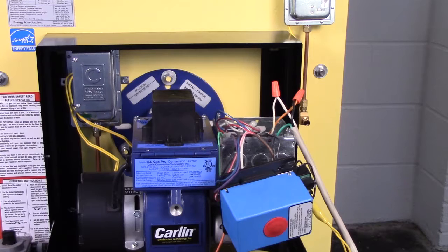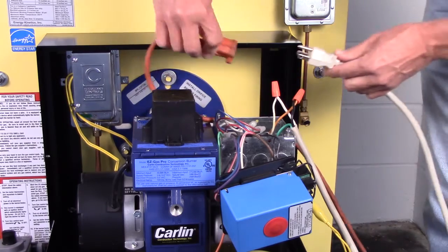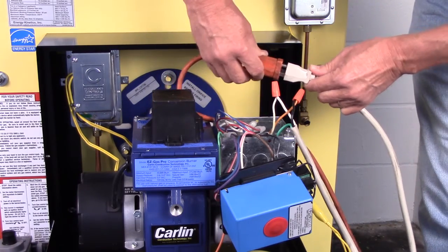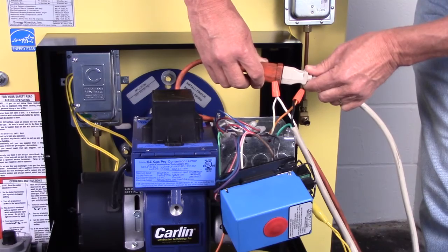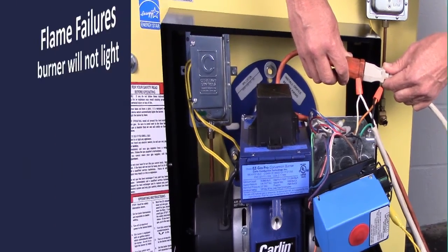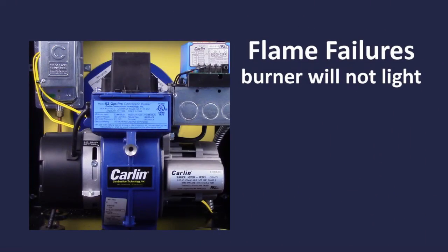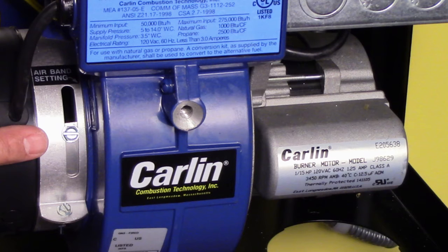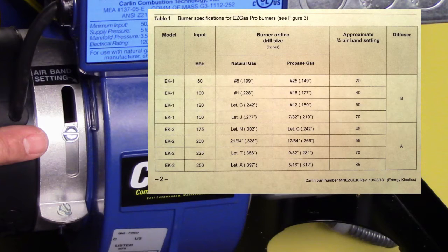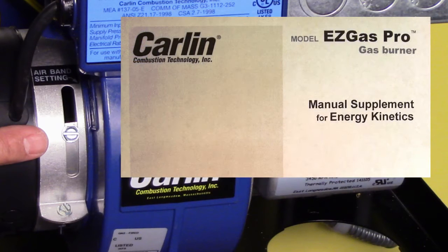To check for a defective motor, disconnect the motor leads from the primary control and apply power directly. Replace the motor if it fails to operate. If the burner motor starts but the burner won't light, begin by checking the airband setting against the gas burner settings table found in the EZGas Pro Manual Supplement for Energy Kinetics.